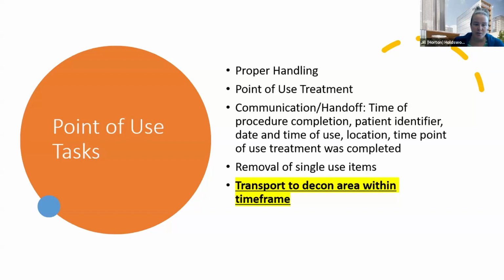Then are you removing those single-use items that you have on your scopes? Removing them before you're reprocessing them. And then I highlighted the transport to decon within the time frame, because this can severely back up your department. And whether you're doing this at SPD or a GI reprocessing area, or a private reprocessing area in a clinic space, if you're not getting it there in the time frame and you're having to do an extended soak each time, it's going to back up the space a lot.